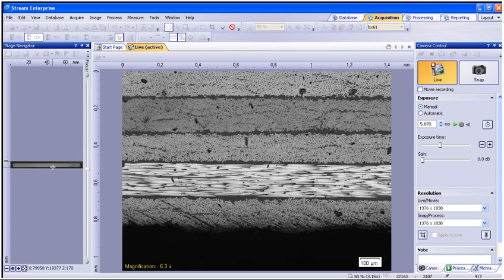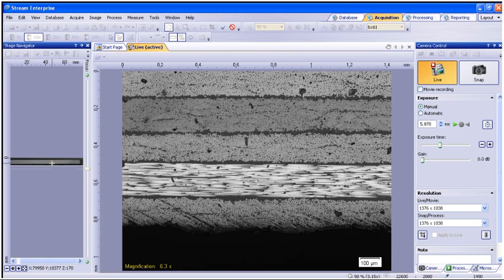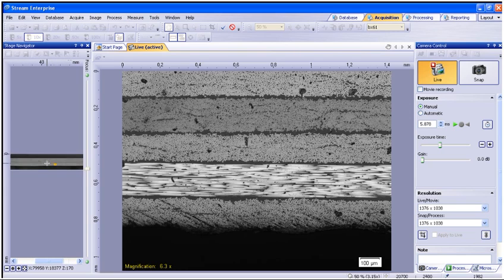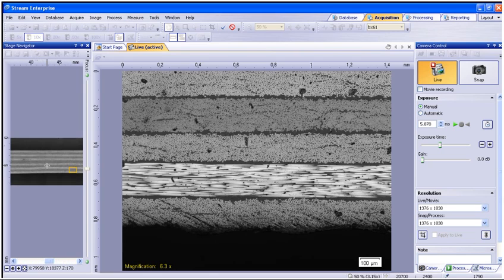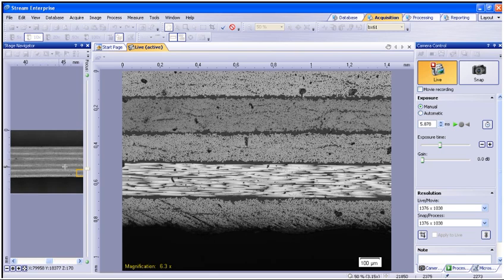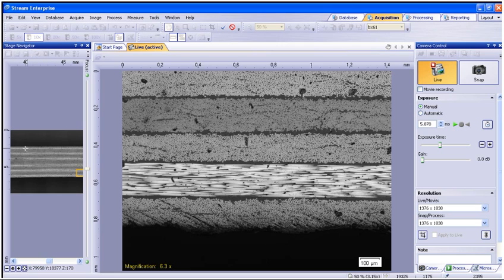The overview image is a low magnification image of the entire stage or sample. Once you have zoomed into the area of interest, you simply point-and-click, then drag the selection box around the area to be stitched for the MIA.